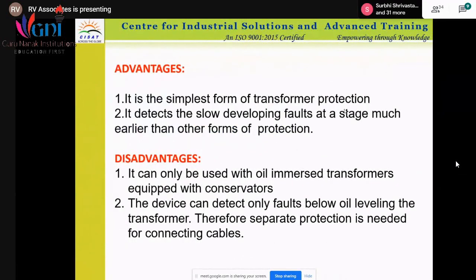As told, the Buchholz relay clears almost 99% of transformer faults. It is the simplest form of transformer protection, but it's very important. It detects slow developing faults at a stage much earlier than other forms of protection. Like if there is a short circuit, there is a heavy current flowing in the transformer, so you use differential protection, short circuit protection, and earth fault protection. Whatever the relay coordination is, they act accordingly. But this is the simplest one.